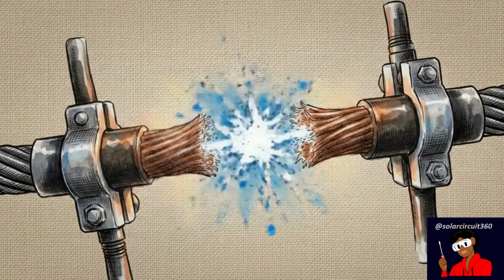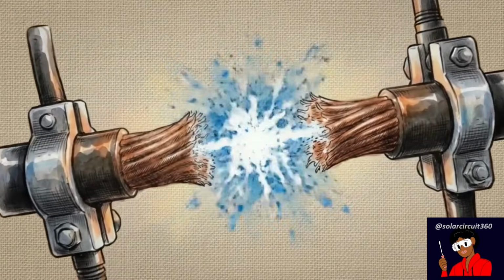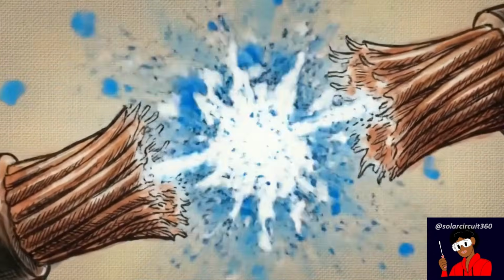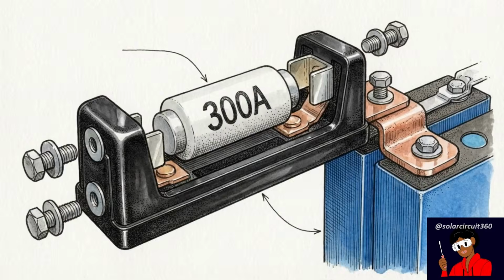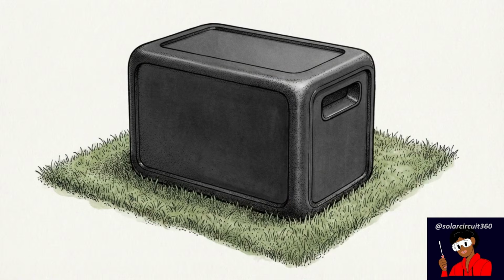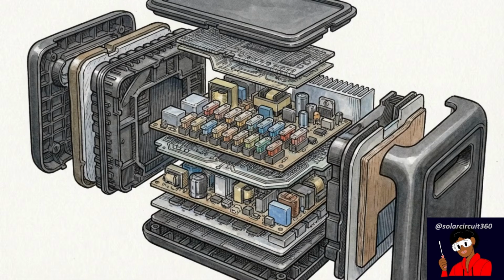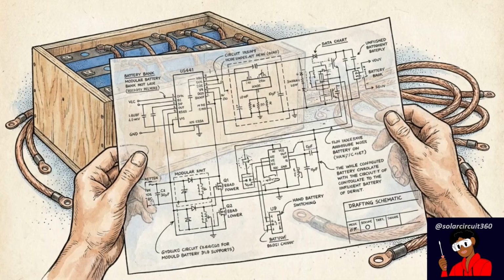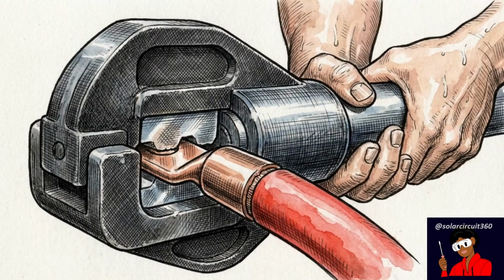Because the voltage is constant, if a connection comes loose, the electrical arc leaping between the cables is incredibly difficult to extinguish, refusing to break. Without rigorous, properly sized fuse coordination placed directly near the battery, these sustained DC arcs will rapidly escalate into severe thermal events and fires. Retail solar generators completely mitigate this risk out of the box. Their internal fuses are closely coordinated and sealed at the factory level, keeping the danger out of reach. Taking control of your system's architecture means ripping off the training wheels. You gain total control, but you must take uncompromising responsibility for its thermal and electrical safety.